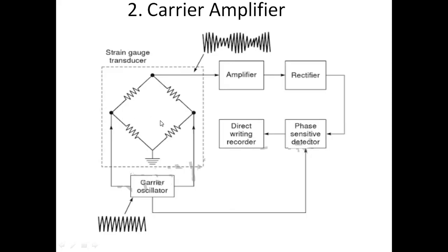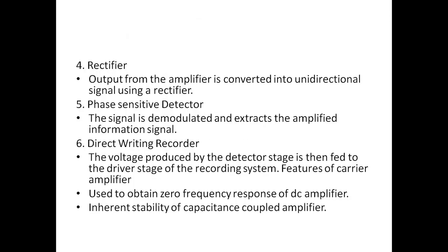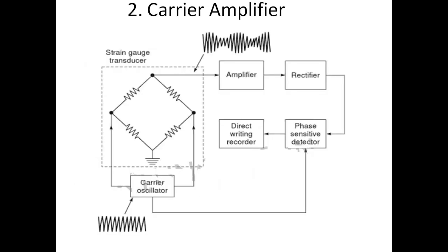The carrier oscillator generates carrier signals. The strain gauge transducer produces modulated signals. The modulation process used here is amplitude modulation. This is a multi-stage capacitance coupled amplifier with three stages of amplification. The signal is then unidirectional. A phase sensitive detector demodulates and extracts the information signal. The voltage produced by the detector stage is then fed to the driver stage of the recording system — the direct writing recorder. This is the complete diagram of the carrier amplifier.